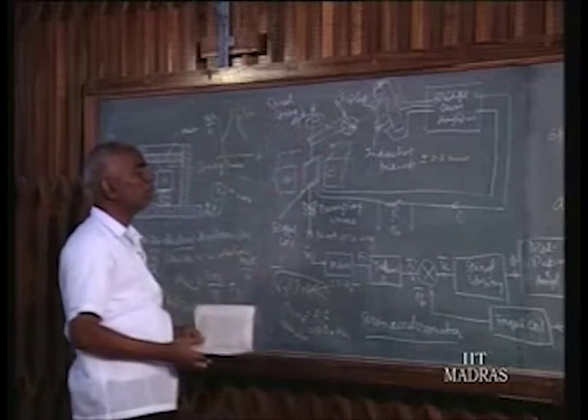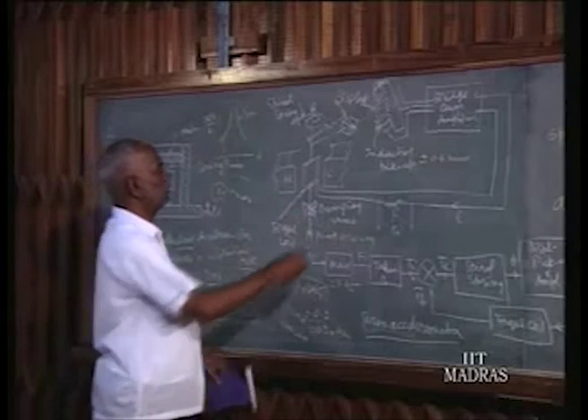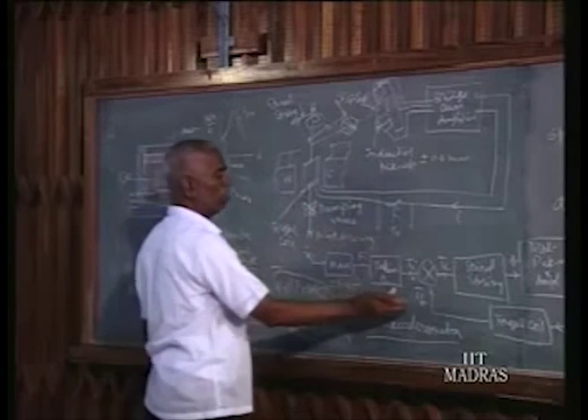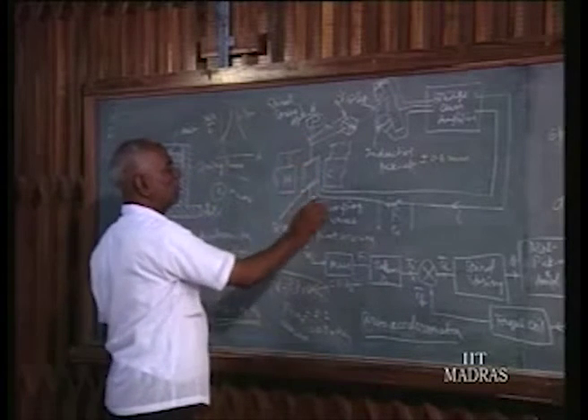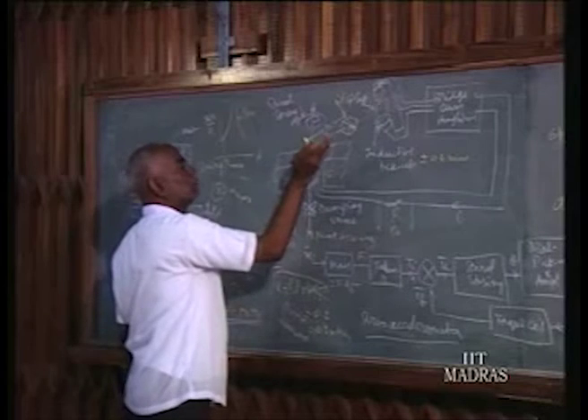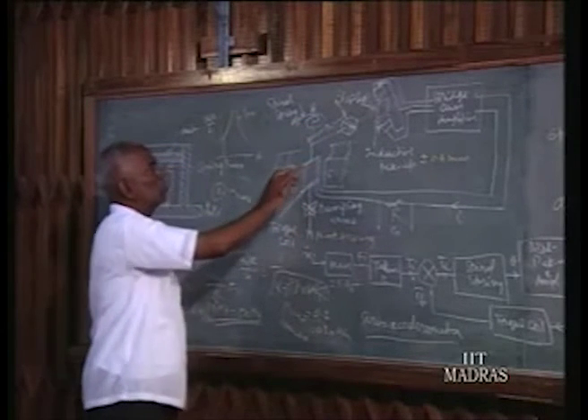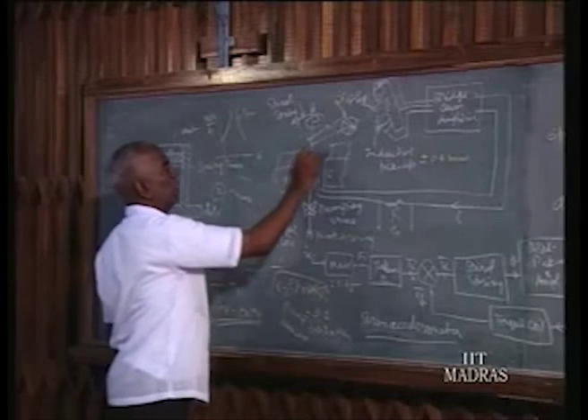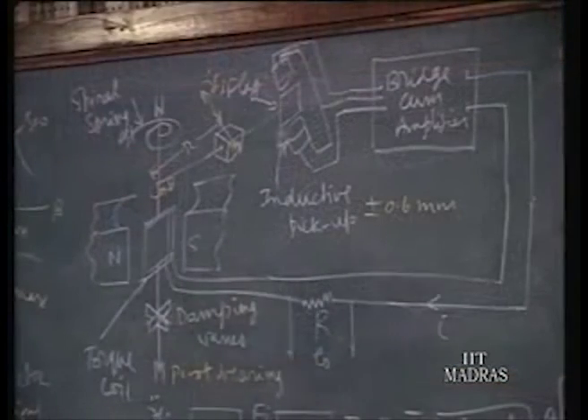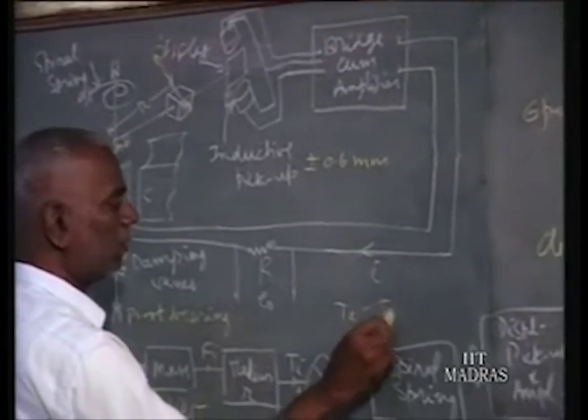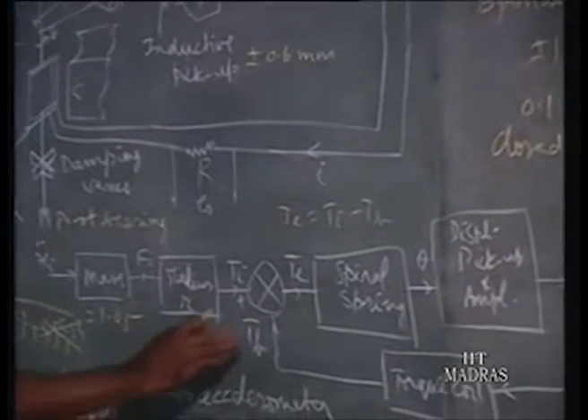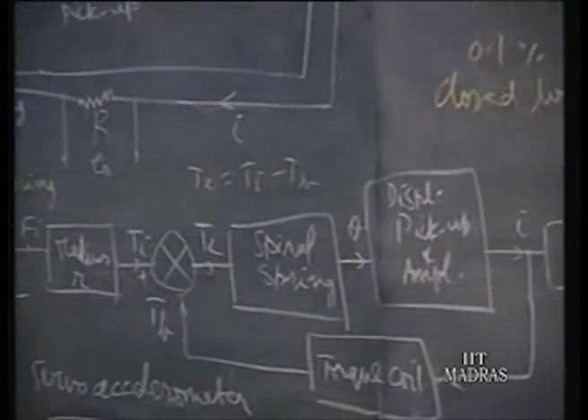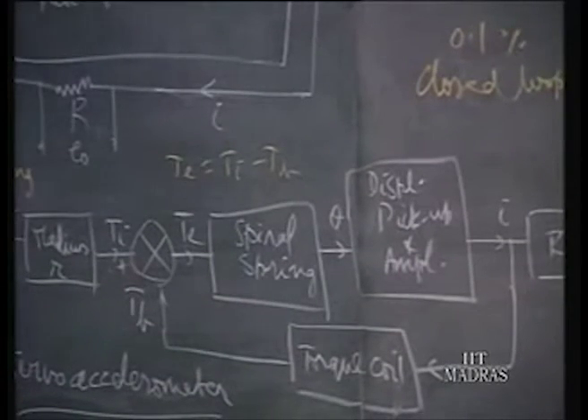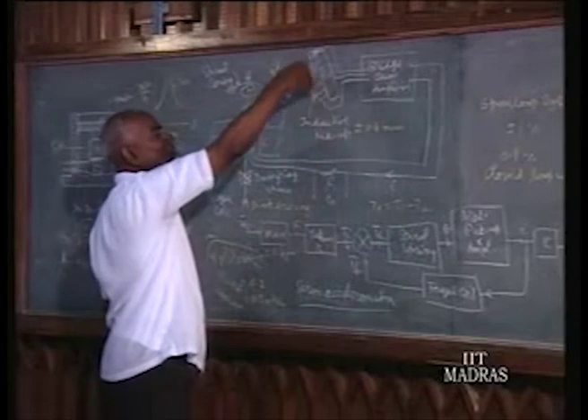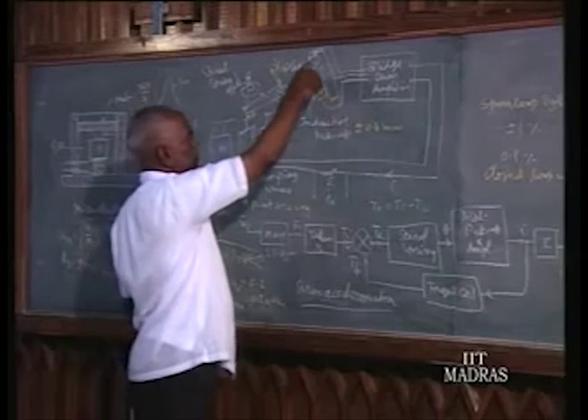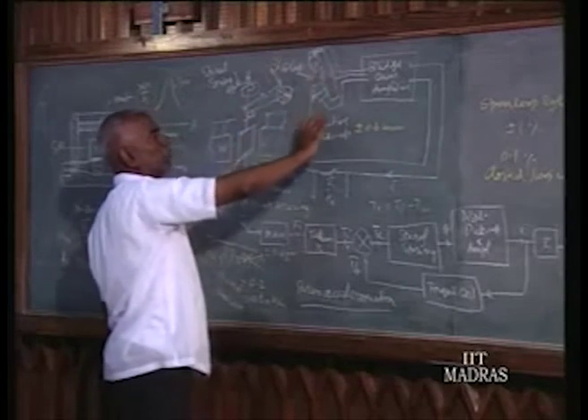So a torque is applied, and there is another torque coming from the current flow, called Tb. When Ti is larger than this feedback torque, the difference between the two torques is converted into an angular rotation theta by the spring. That is, Te is equal to Ti minus Tb. So the difference between the torques is taken up and converted into angular rotation theta, and theta times the length of this lever gives a displacement in front of the two inductive pickups. And when it moves, we know how inductive pickups function.